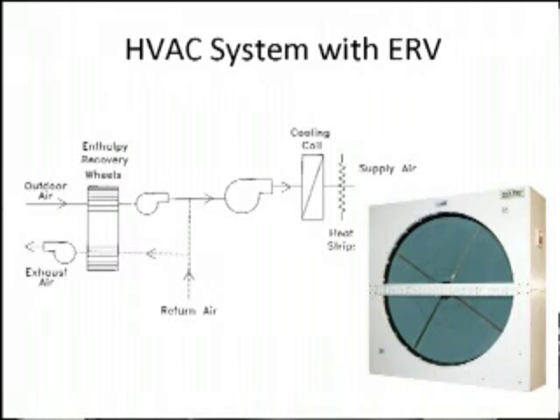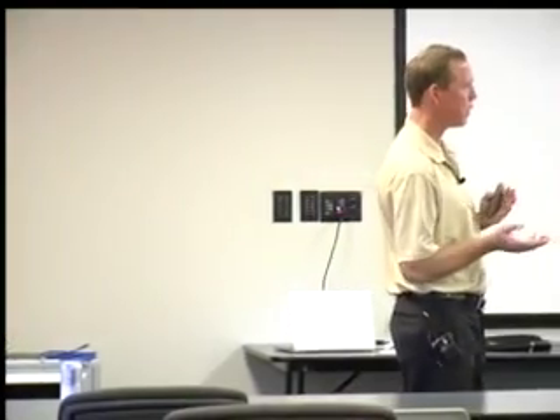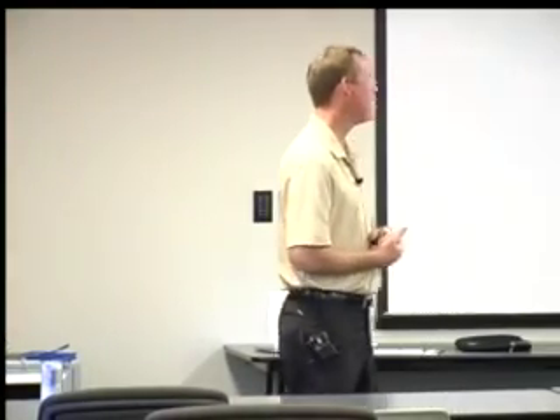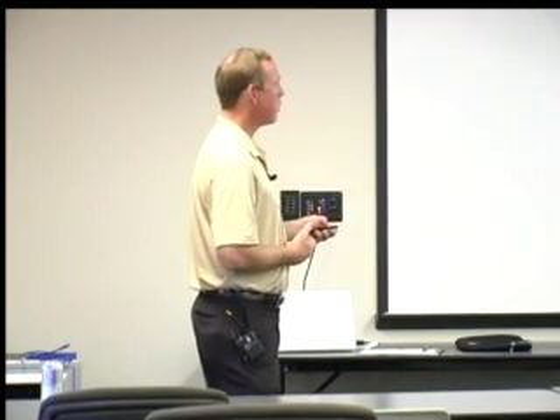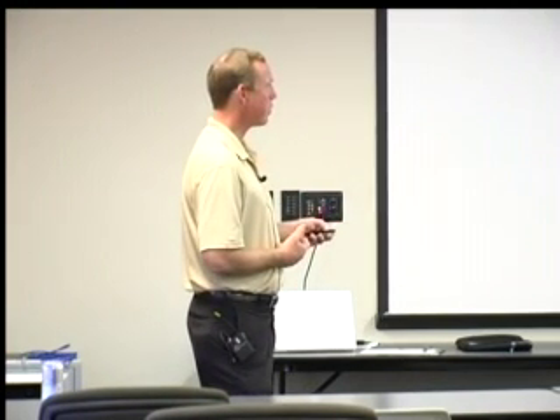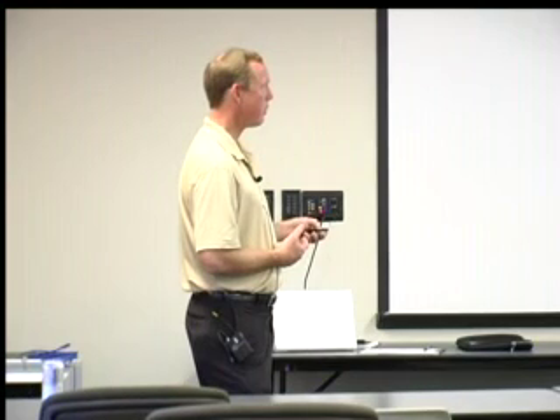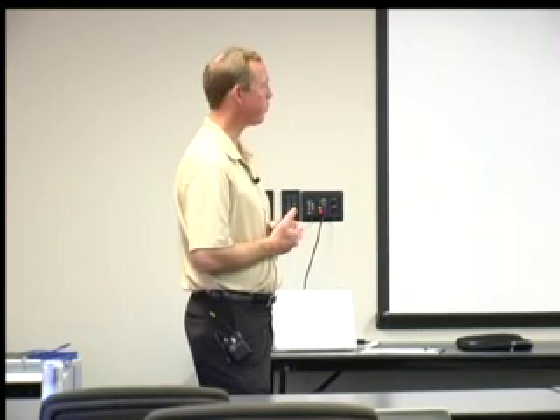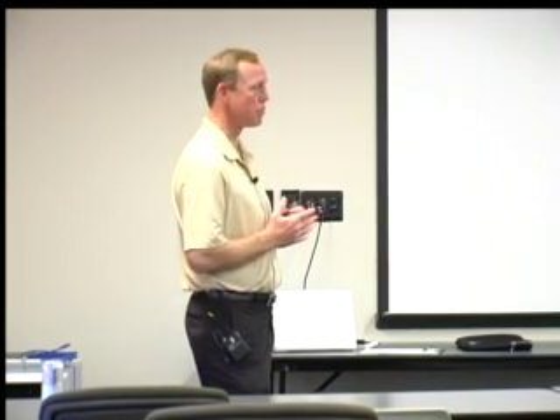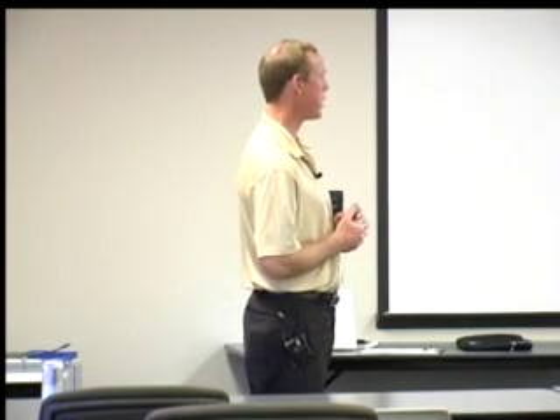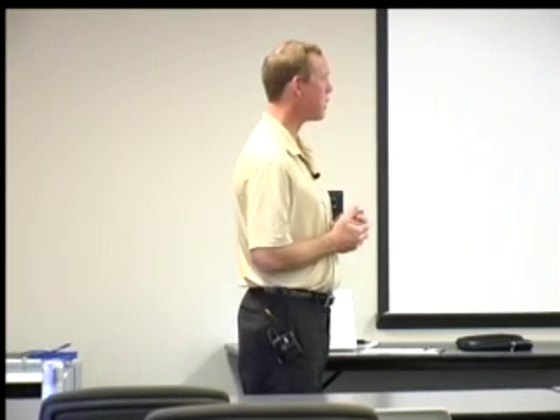And this cold air coming out from the building, our building's being conditioned at 73, it comes out, passes across this membrane, and warms that membrane back up. And so that's how that works. It transfers the heat from the air coming in to the air going out. So with that system, maybe this heat strip could be completely eliminated, depending on how you set it up. If you get the right mix of temperatures and everything, that could possibly be completely eliminated, and be big savings for you.